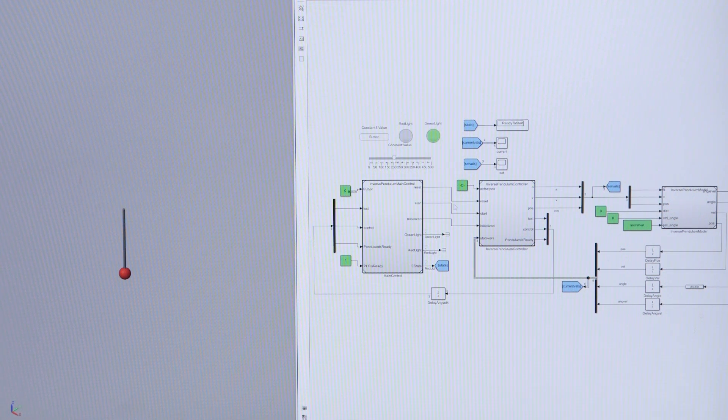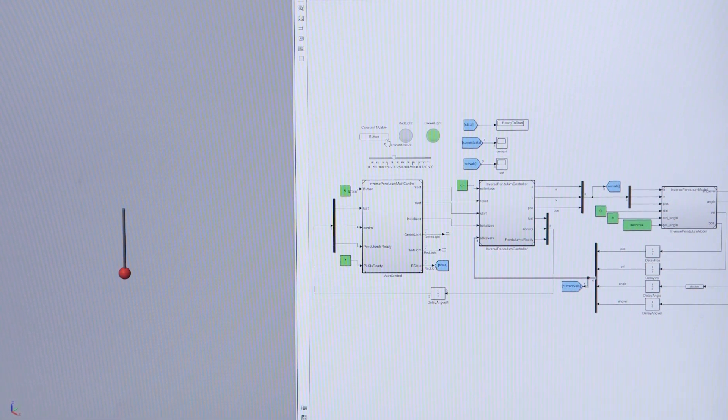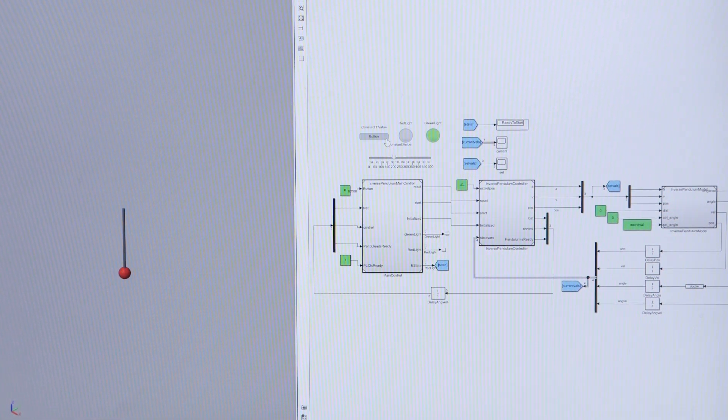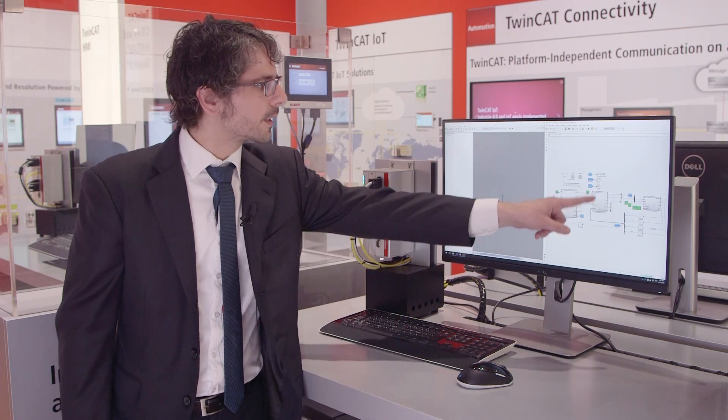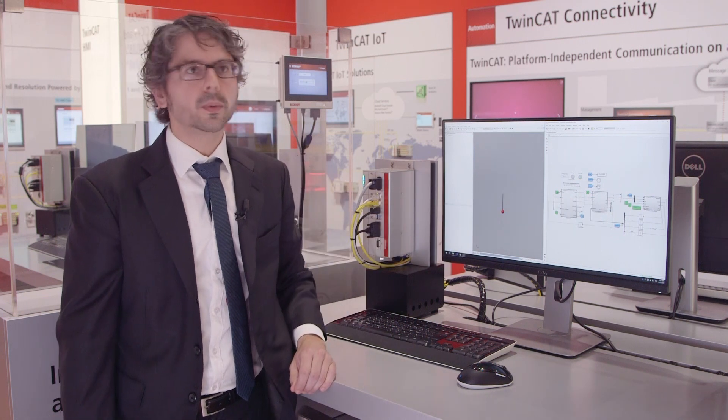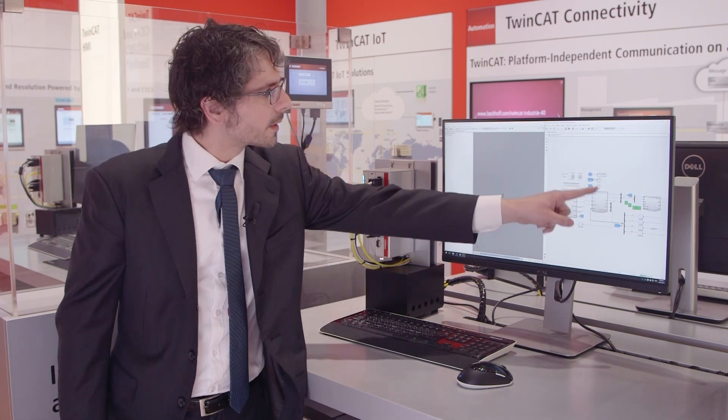With the interface for MATLAB Simulink, we also support the model-based design process, starting with model-in-the-loop simulation in Simulink with both the controller and the control system. Then we simply integrate the controller into TwinCAT and use the interface to establish ADS communication with Simulink where we can carry out a software-in-the-loop simulation.